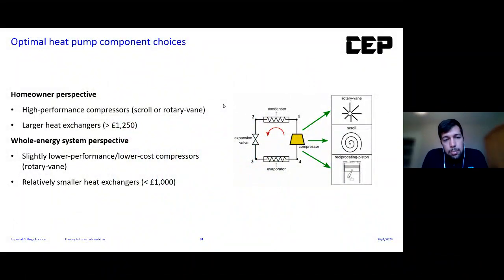In terms of components, it's worth mentioning that high performance compressors are usually scroll type, at least for UK weather, though some rotary compressors are used as well. It seems optimal to go for relatively high performance compressors and relatively large heat exchangers from the homeowner's perspective, while from the energy system perspective, that optimal point shifts slightly to lower performance components and smaller heat exchangers.